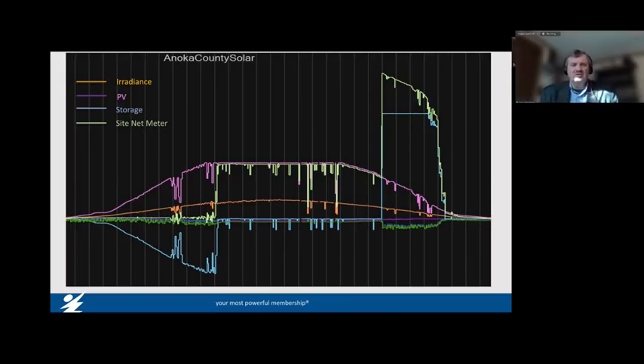When we dispatch this, all we do is the day before send a signal—a couple clicks of a mouse—to turn the batteries on the following day. At midnight they turn themselves on. When the sun comes up, they charge up. We then put in a schedule as to when we want to discharge them during that day. Then they'll discharge, and the following operation to recharge back up to 50% the next day is all automated. So we tell them when to turn on, enter a schedule, and the rest of the whole process is fully automated. It's pretty neat.